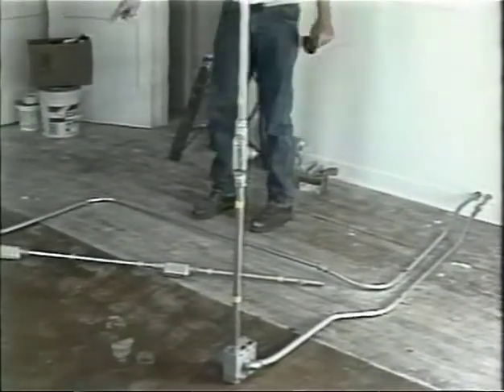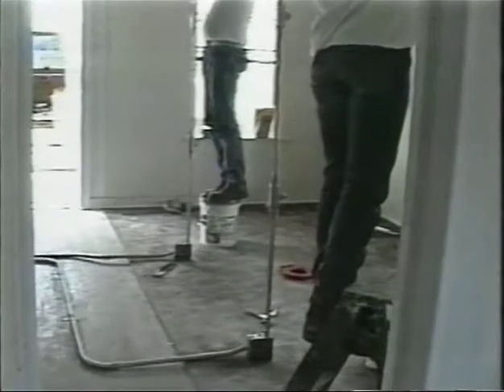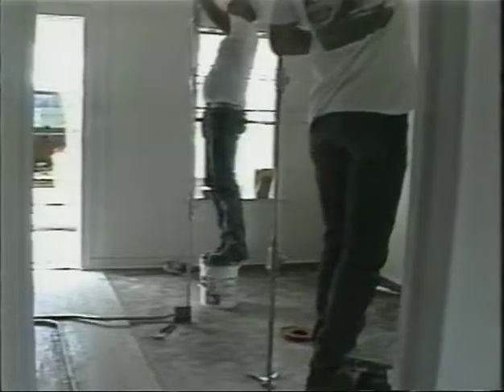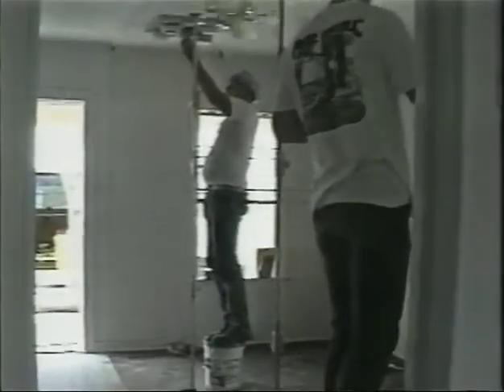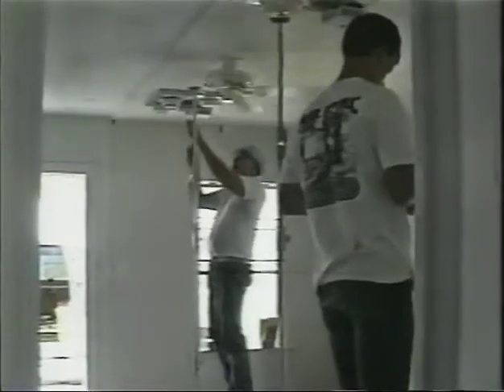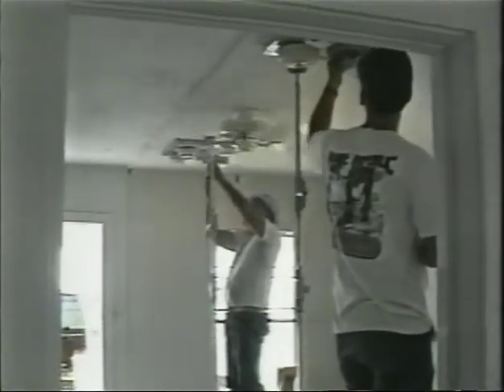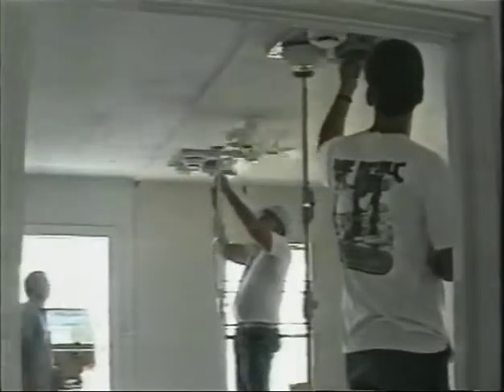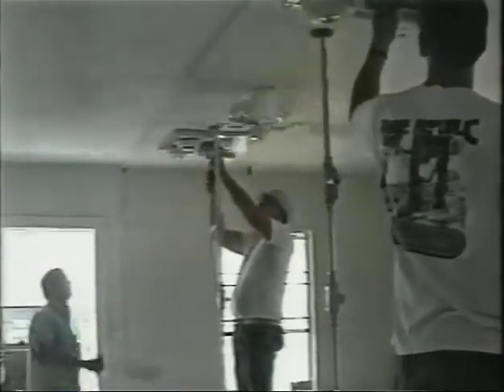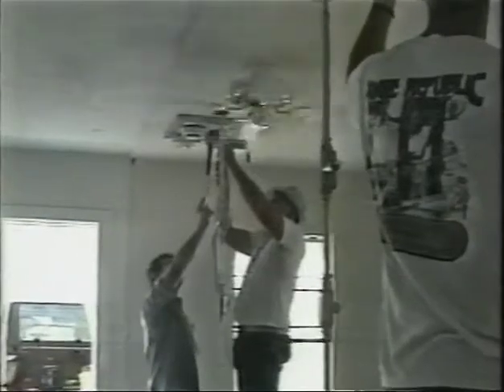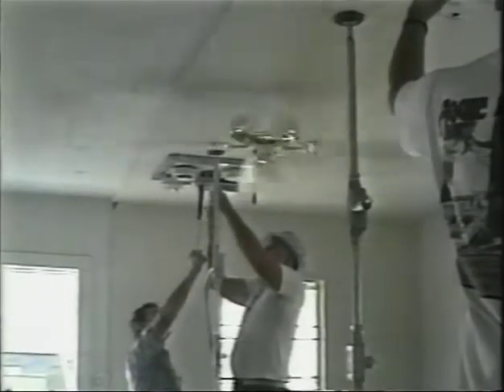3/4-inch plywood was installed to protect the floor. In order to measure obscuration, flood lamps were installed at 2 different levels in the living room and hallway. Photoelectric sensors located on the opposite wall were connected to a data recorder. Prefabricated panels housing the various detection devices were mounted at 2 locations, equal distance from the fire, on the living room ceiling. Because many residences employ ceiling fans, a fan was installed to determine what effect, if any, its operation would have on the performance of the detectors or the fire growth.